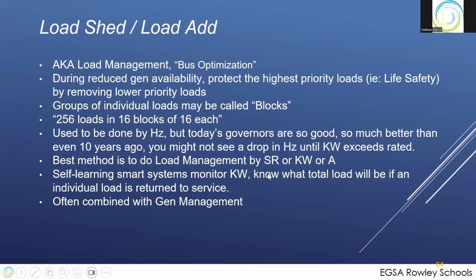Load Shed Load Add is a way to protect a system. So let's say that you have 5 gens and 5 loads. You bring all 5 gens on, all 5 loads are up, everybody's happy. Now your load is low, you don't need to have all 5 gens. So you back off 2 of them. So you're going to have 3 gens feeding all 5 loads. Well, let's say you lose a gen, and it might just go into alarm and come off slowly, or it might be a trip stop fault condition. In that case, you're overloading the generators.